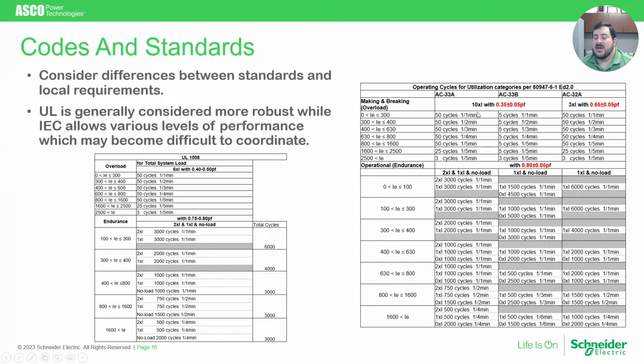As you can see in this example, a difference of an IEC qualification to the AC33A utilization category requires 50 cycles of overload testing for most ampacities, while one step below that, the AC33B, only requires 5 cycles of overload testing. So the performance and testing required to gain the qualification is significantly different, and you have to pay very close attention to product qualifications, which category and utilization level you are specifying the product for.